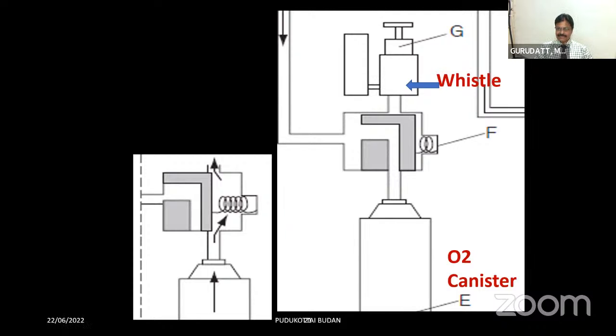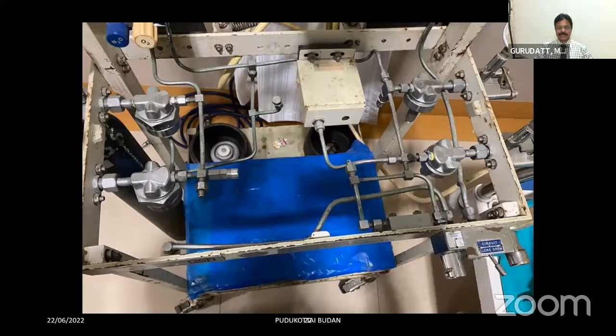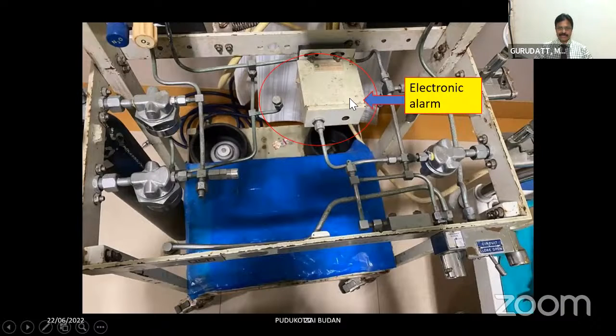So because of these, later in Boyle's Mark III and the Boyle's Basic itself, electronic alarms were introduced. You can see this electronic alarm in the Boyle's Basic, and they are operated by cells. So you had to check every time before you start using this anesthesia machine whether the cells are active or not. Otherwise, you have to replace the battery. Whereas in modern workstations, we don't have to replace this battery.